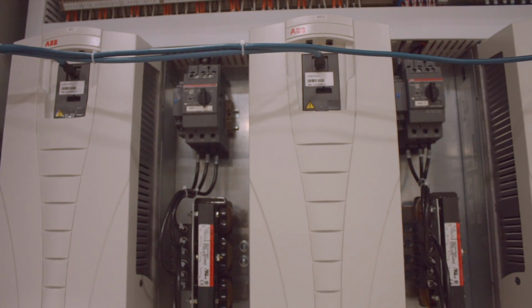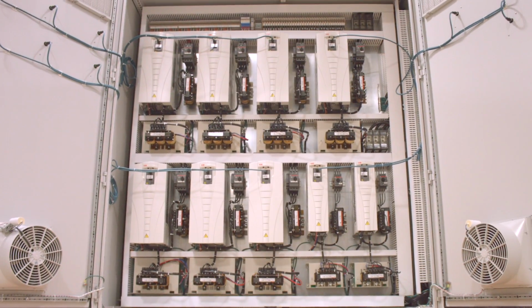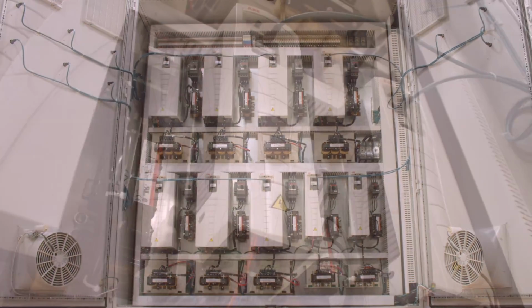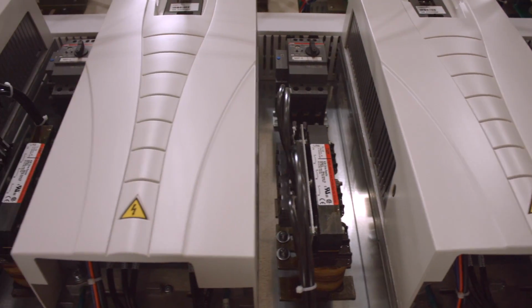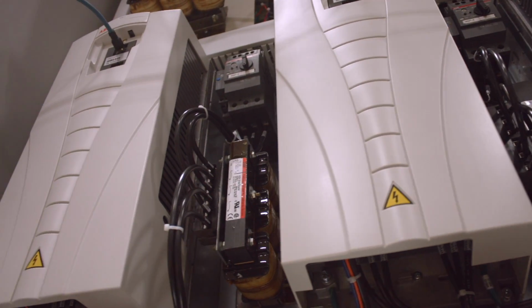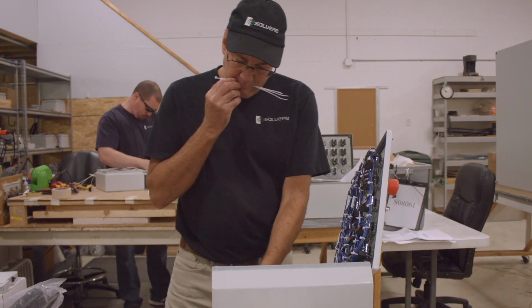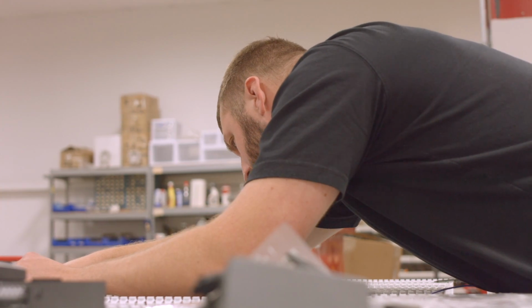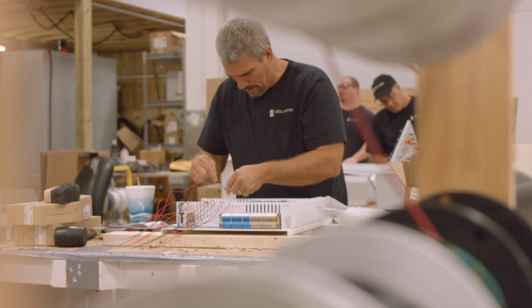Line reactors, load reactors and filters, RFI and EMI filter to reduce high-frequency noise generated by VFD, braking resistor to dissipate bus voltage, surge suppression for 3-phase power and control signals, voltage monitor for phase loss, phase reversal, under voltage and over voltage.